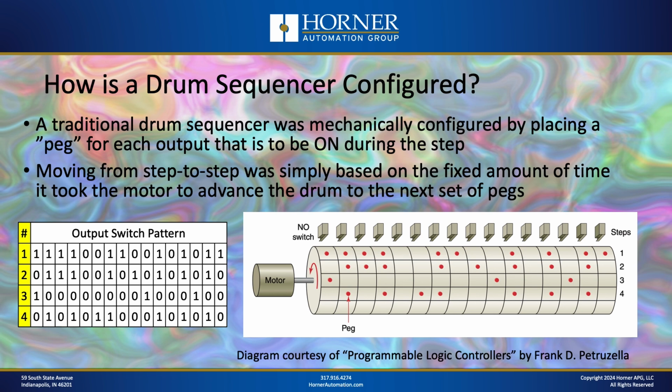Now you're thinking, this looks pretty old-fashioned, why would I ever want to use that? Well, if you think about it, there are a lot of applications that have a series of sequential steps or stages where different outputs can be on in different stages, and either a specific input will cause you to move from one stage to the next, or maybe a specific amount of time will cause you to move from one stage to the next, or maybe time and an input changing will cause you to move from one stage to the next. So these can be really useful ways of controlling sequential type machines.